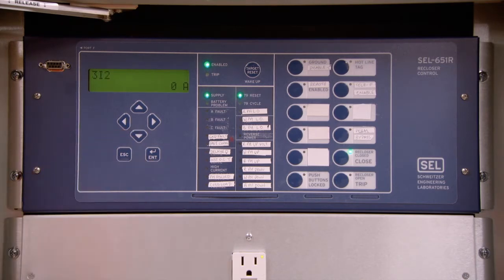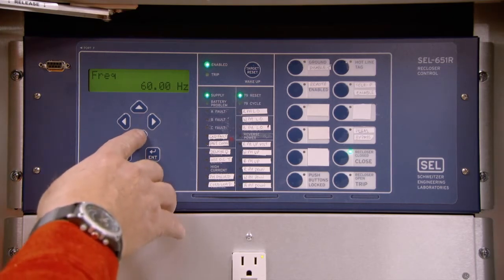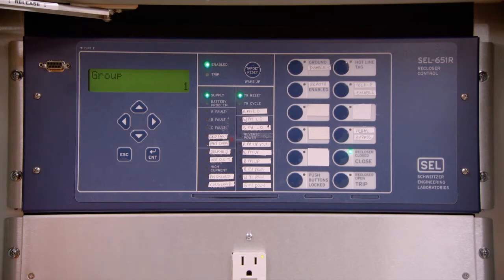The next down arrow screen displays 3I2 that indicates the negative sequence current. The next down arrow menu displays the frequency at that trip. Finally, the last screen will indicate what group setting that you are using.